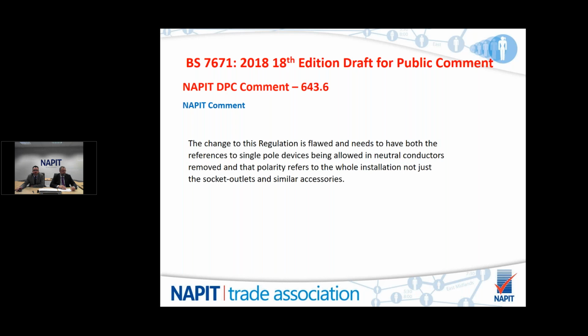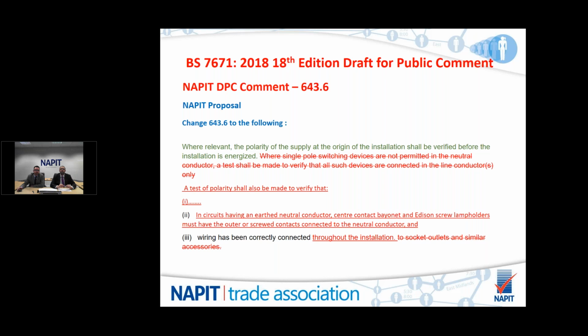So our comment on this is there needs to be a change to this regulation. It is flawed. It needs to have the references to single pole devices being allowed in neutral conductors removed, and it needs to say that the polarity refers to the whole installation, not just the socket outlets and similar accessories. And it needs to be made clear what the polarity covers and what it should be checked for. So as Frank said, we need to be looking at polarity and where we need to be checking.